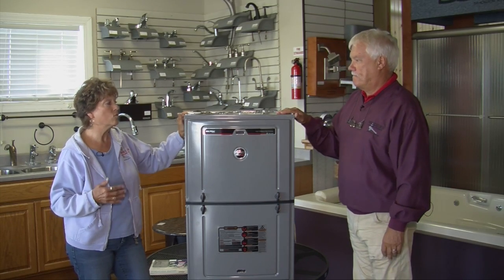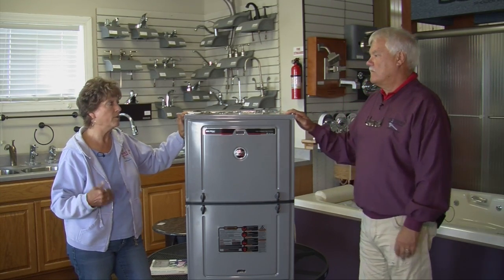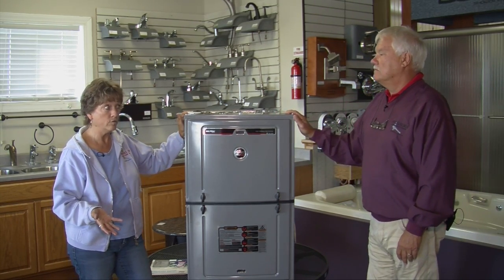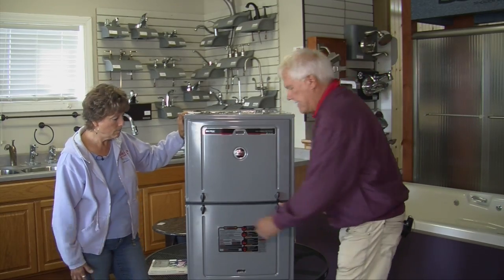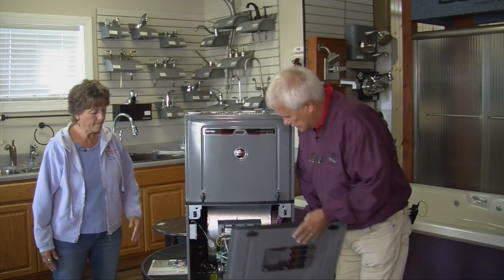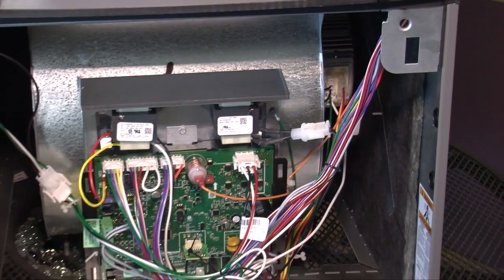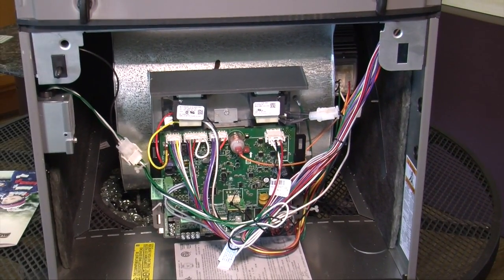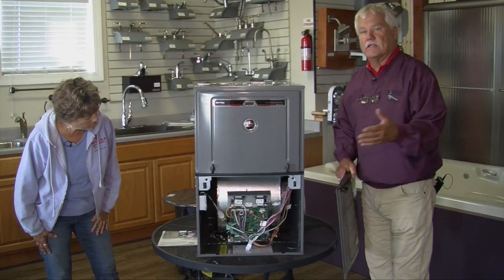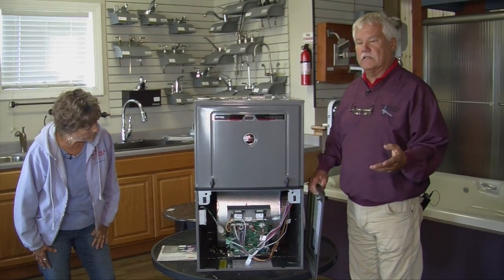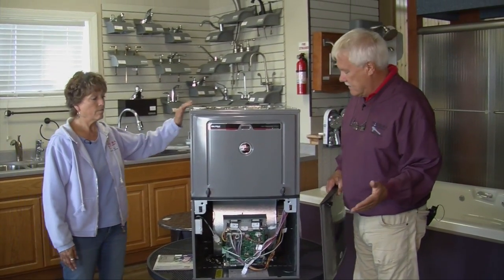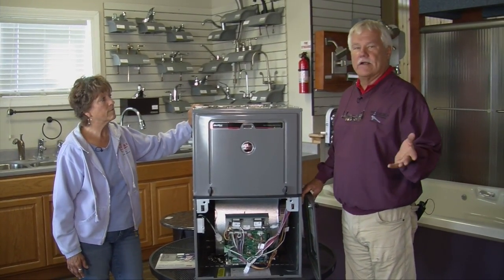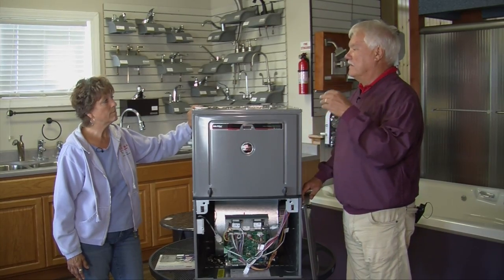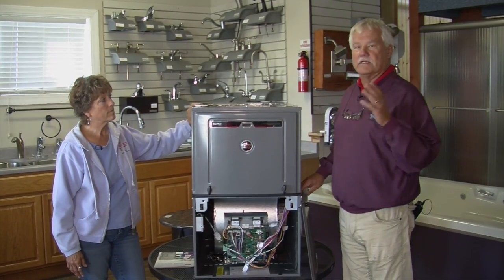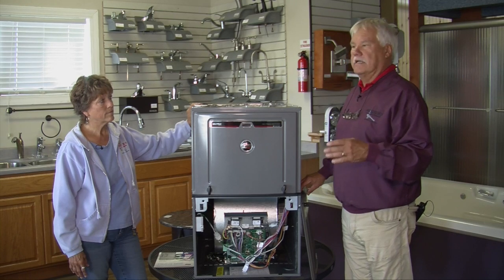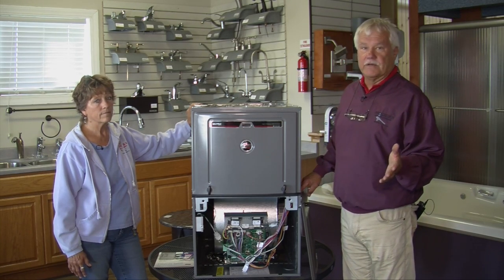So the heat exchangers are obviously important, but there's also ECM blower motors. That's right. And modulating. That's right. In the bottom of the furnace here, we've got our blower section, and there's a motor inside of this blower housing. Like Kathy said, it's called an ECM blower motor. It means electrically commutated motor, and that means that it just doesn't go on and off. It cycles at a variable capacity. It delivers the exact amount of air that you want, and it's like 20% more efficient than a regular 4-speed blower motor.